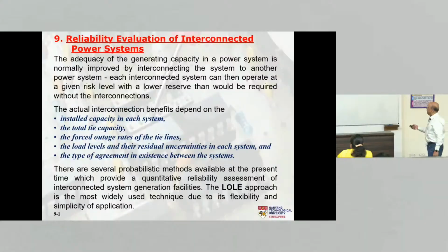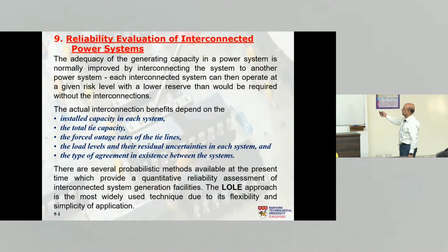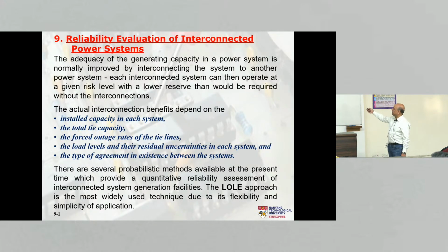So the adequacy of the generating capacity can be improved by interconnecting the system to another power system. Intuitively also we can see that each interconnected system can then operate at a given risk level with a lower reserve. If I have my own system with my own reserve, and I connect my system to another one and take some benefit from there, then my reserve can be lower, because I'm taking some additional capacity, correct? So reserve would be lower, and if there is no interconnection, then of course I have to maintain a certain reserve. It will never be lower than that.